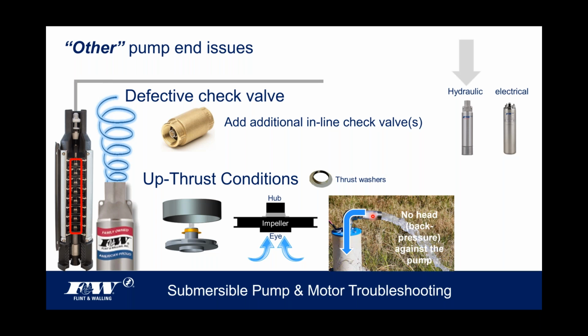And so this water coming up out of the top of that casing at that time is horrible looking, terrible looking. And they'll leave that run, open discharge like you see down there, until that water clears up. Then they'll hook it on up to the pressure tank and let it come into the house. But that whole time that they're running open discharge like you see here, you will be in upthrust. So you would like to make sure that you've got a bearing system or a washer in there capable of taking that bit of abuse that it's going to see on an initial installation.